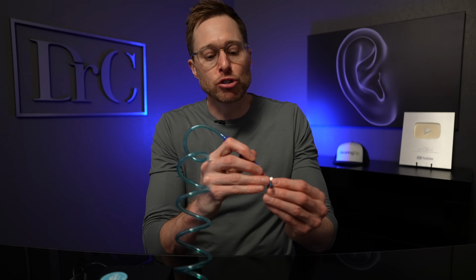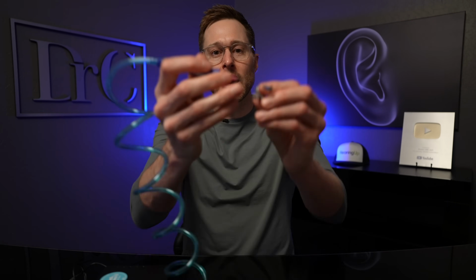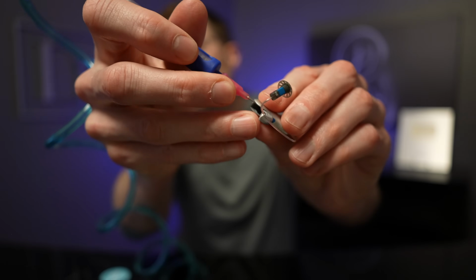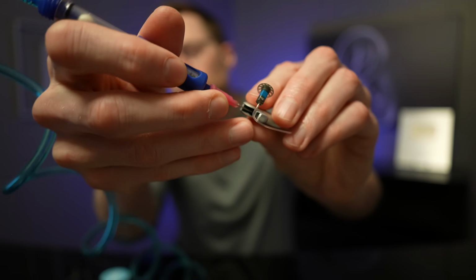and so what I want you to do is go ahead, open that up, and you want to be very careful because you don't want to bend the contact points to the battery inside of there, but you're just going to go in there and suction out all the debris that has worked inside of that hearing aid. This will give you some level of understanding what I'm doing here, and I'm just being very careful not to bend those contact points inside of that battery compartment.